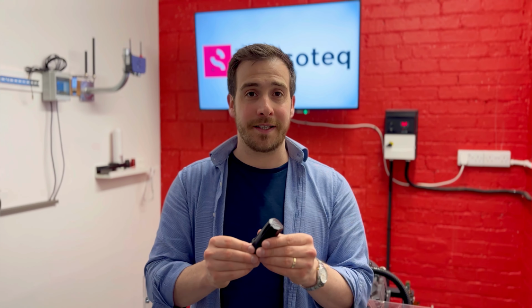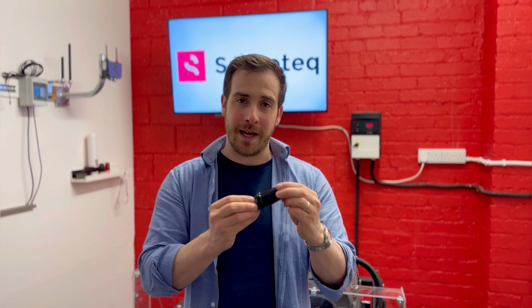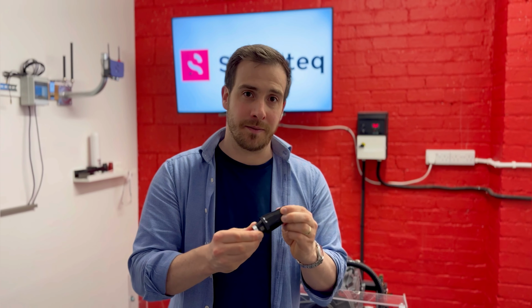You typically want that to be around the center of gravity or center of mass of the device. That means that you're going to get the absolute best response without any harmonics coming in from the actual weight of the sensor. A heavier sensor is going to attenuate some of the signal, it will dampen it, whereas a lighter sensor is going to make sure that you get the absolute best, cleanest signal coming out of your accelerometer.